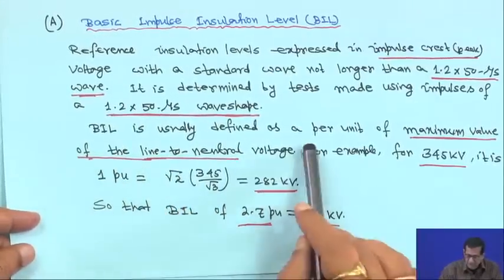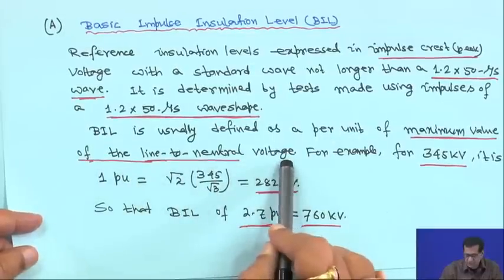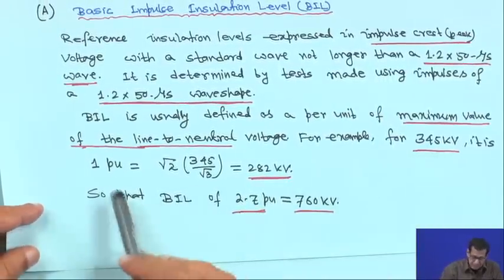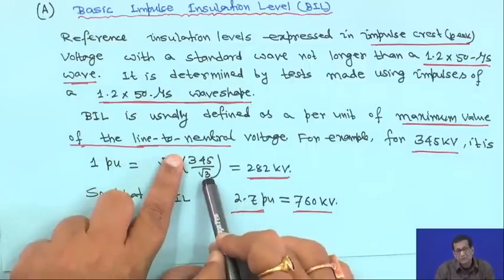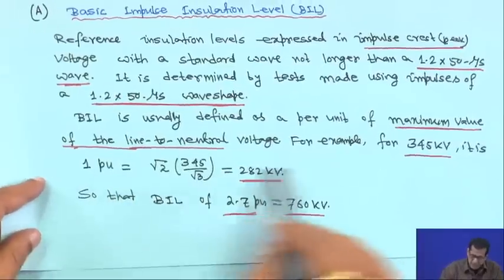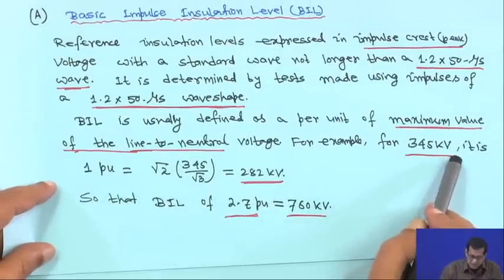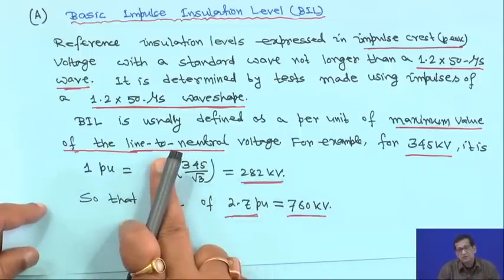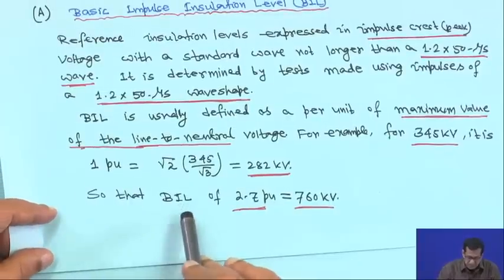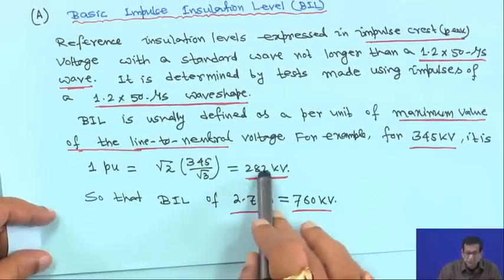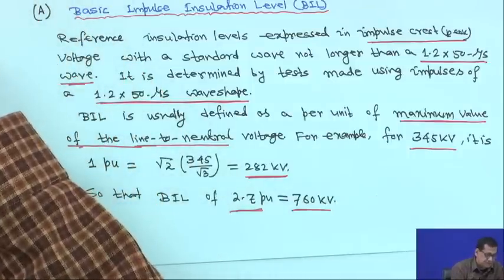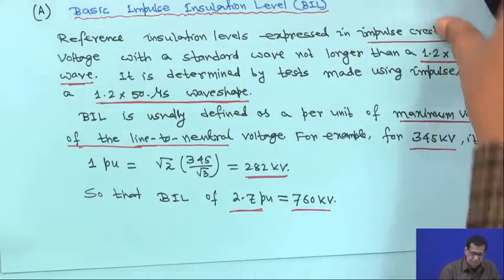BIL is usually defined as a per-unit value of the maximum line-to-neutral voltage. For example, for a 345 kV line, 1 p.u. equals 345/√3 multiplied by √2, giving 282 kV as the peak value. So if the BIL is 2.7 p.u., that means 2.7×282, which gives 760 kV.